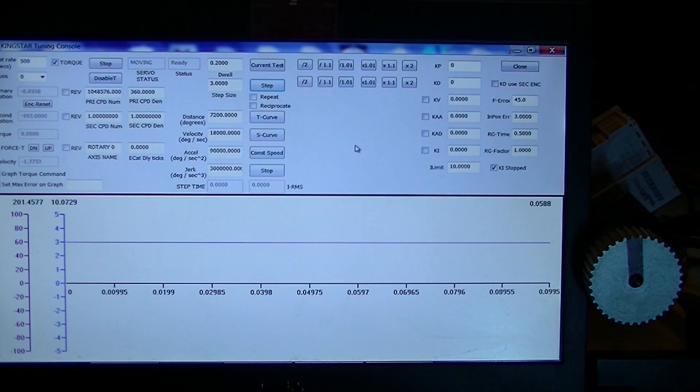In the initial setup, you can see a motor off to the right with a 1 million count encoder. We set up the encoder resolution as 1,048,576 counts against 360 degrees. This is a numerator and denominator, and you only have to set this up one time. Then forever you're working in degrees, at least for this.